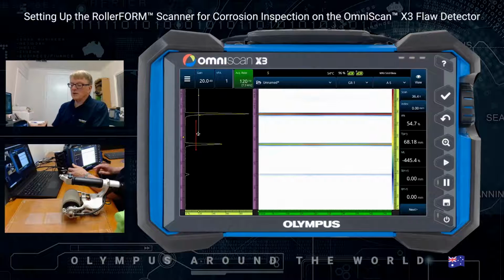Just going to move that gate out of the way so that where the interface gate meets the interface echo will be the 0 point. So that's our 0 point as we would find if we did a wedge delay. In this case, it replaces the wedge delay, and it does this for every single beam, every VPA that we have across our part. And then because it's a 0 there and the scale is actually exactly the correct scale, assuming your velocity is correct, where you see the signal, you can actually immediately read off the measurement if you need to. It certainly helps with troubleshooting.